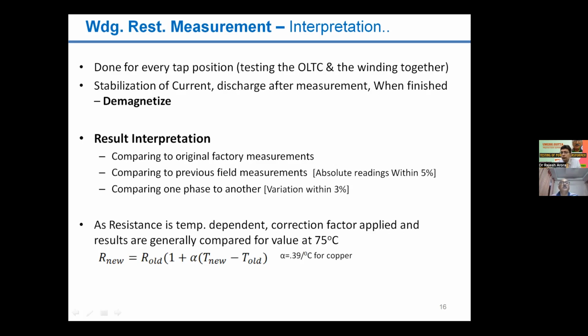And result, how you compare the results with the factory measurement values or the previous values which you have recorded during your previous tests, previous years. Comparison is done with respect to earlier reports, and the variation should generally be around 3%, and compensation is done accordingly. You may test the transformer at different temperatures, but while performing this test, it is very important that you compare the test results at the same temperature level.